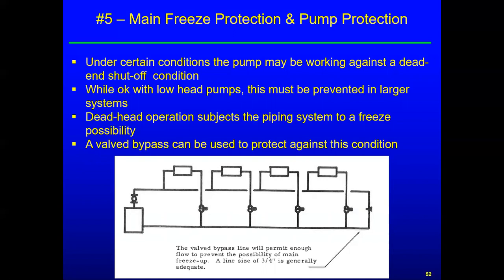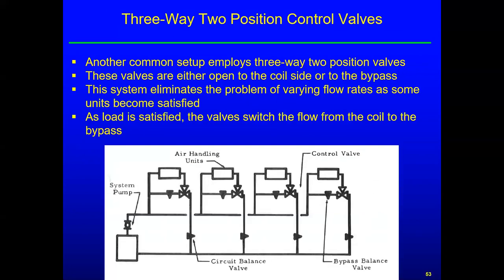That valve bypass could stay shut, and you could have a pressure sensor on it so that if all these other valves are closing and the pressure goes up to a certain point, then that valve opens, so that you don't just push water around that loop all the time when it's not serving a purpose. So anyway, that's a possibility. Okay, now we can move on to three-way two-position control valves. A three-way valve can modulate, just like the two-way valve can, or it can just snap back and forth. So the first couple slides here are two-position three-way valves, which means that you either get full flow through the coil or full flow through the bypass.